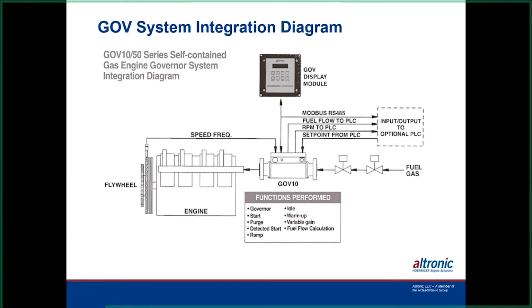And then you've got the Modbus communication that comes out of it that you can read a lot of the shutdowns and alarms and stuff on, and also control the speed with it. And then it's also got a flow capability. It's a 4 to 20. You can scale it, and then you also can read the RPM on it too. It will give you another 4 to 20. You can scale that for the speed also.